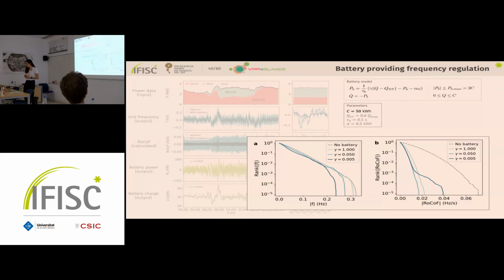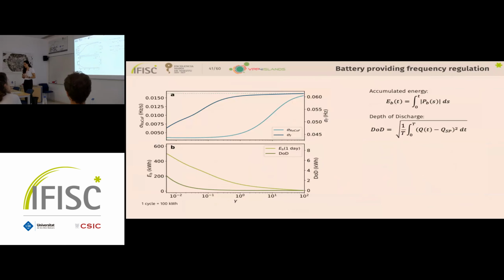We performed a more systematic analysis for more gamma parameter values. We have here the standard deviation of the ROCOF and of the frequency, as well as the energy accumulated by the battery in one day and the depth of discharge for different gamma parameters. As we decrease gamma, we are able to reduce both the frequency and ROCOF fluctuations, but this comes at the cost of the battery accumulating more energy and having a larger depth of discharge.